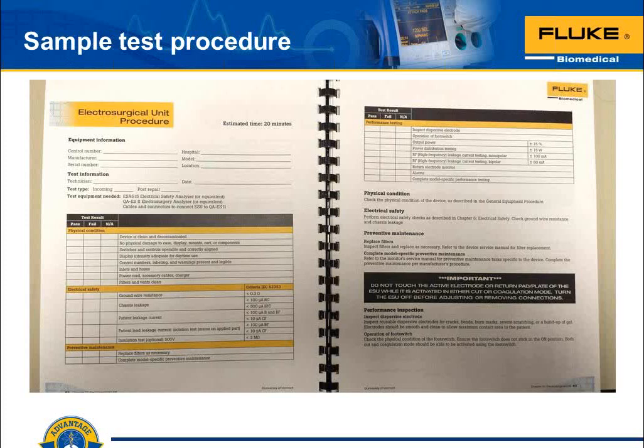behavior would be that you would begin to see, as the test load increases in resistance, you would expect to see the output power begin to drop off. And if not the output power, you will see either voltage or current drop off, depending on which of those two values or parameters the electrosurgery unit generator design is controlling. So power distribution test really helps us test those circuits.